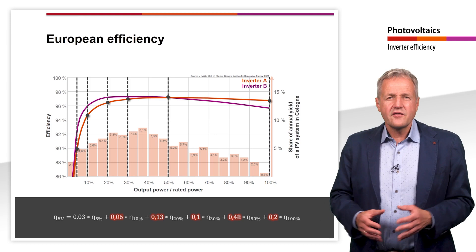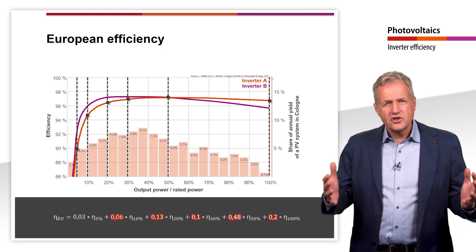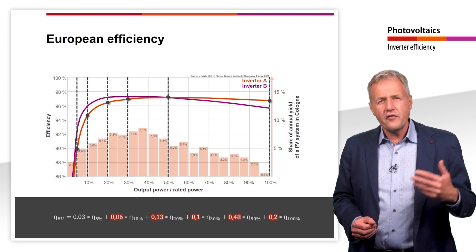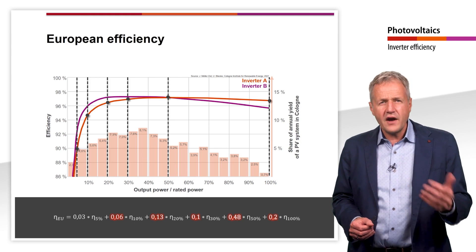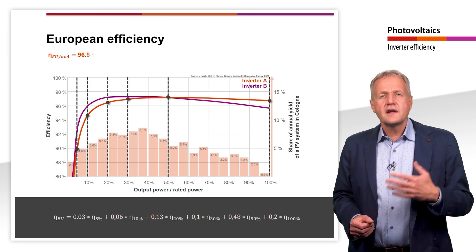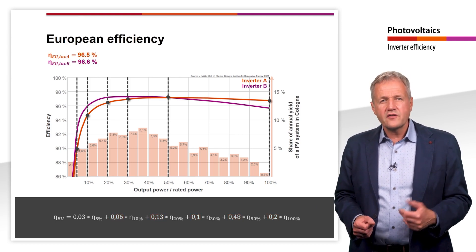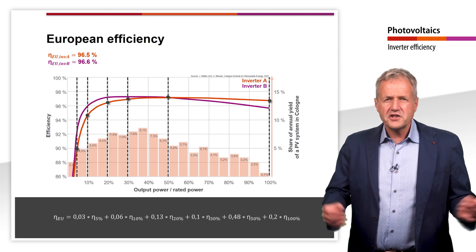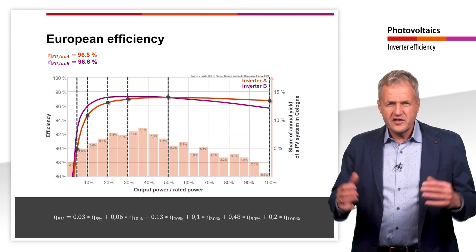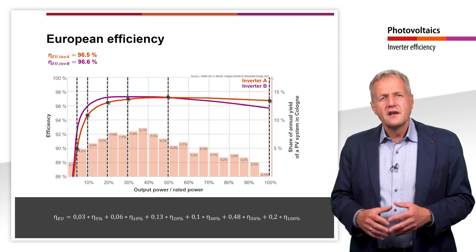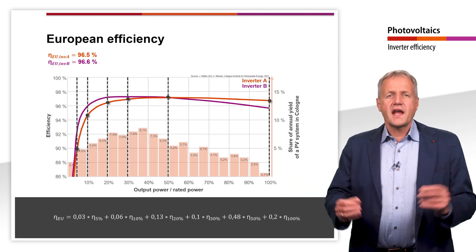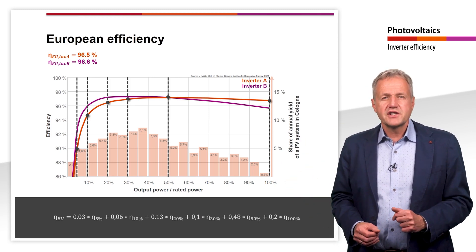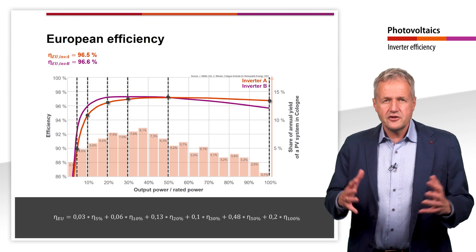Applying this formula to the inverters shown here results in a European efficiency of 96.5% for inverter A and 96.6% for inverter B. The European efficiency is of course only an approximation, since Central Europe covers a large area in which regionally very different irradiations are to be expected.